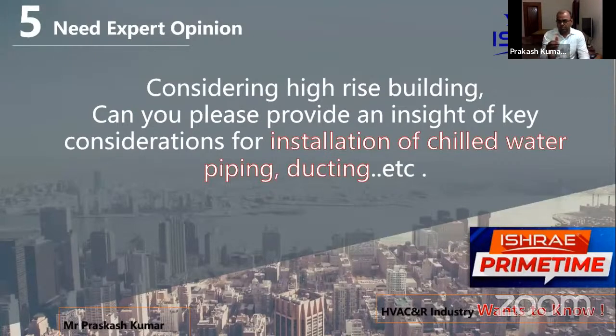So the amount of water going to the lower floors and to the upper floors, the travel distance might vary. It may so happen that the water going to the upper floors might experience more pressure drop. So what we do is we provide a motorized valve and a restriction orifice plate at the inlet of each AHU to ensure that the pressure loss across all AHUs is the same.